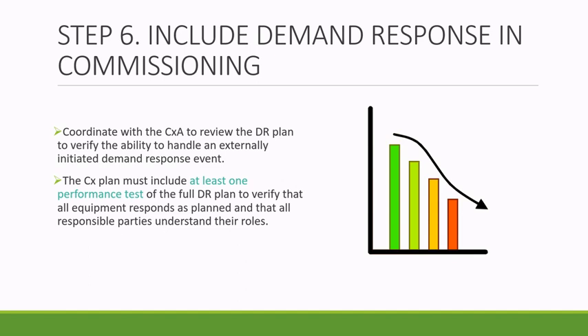Step 6 is to include demand response in commissioning. The project team must coordinate with the CXA to include a review of the demand response plan in the commissioning of the building system test procedures to verify the ability to handle an externally initiated demand response event. The CX plan must include at least one performance test of the full demand response plan to verify that all equipment responds as planned and that all responsible parties understand their roles.